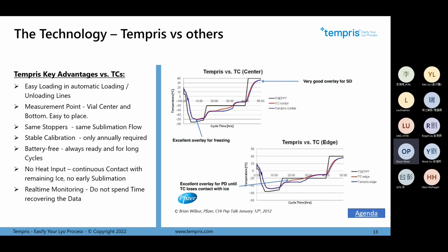The measurement point I mentioned uses the same stoppers. This is very important. We are not changing the sublimation flow. Of course, we always have some body inside the vial, and this must always be considered, even when it's a very thin one like thermocouples. But we are using exactly the same stoppers as the other vials, so we have the same sublimation rate, the same space for getting out this humidity or sublimation flow from the vial.